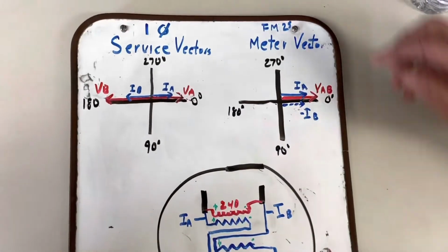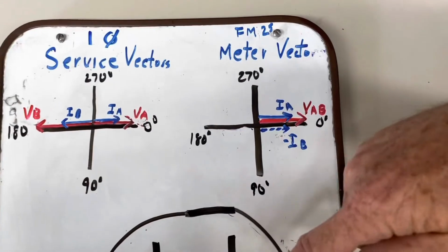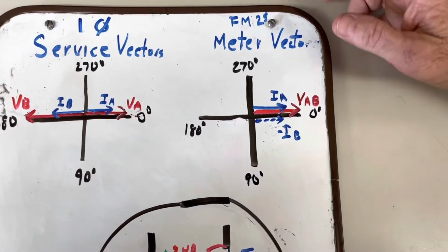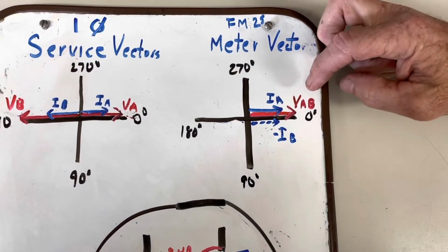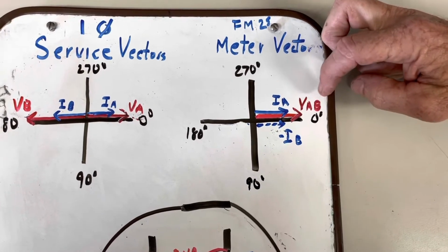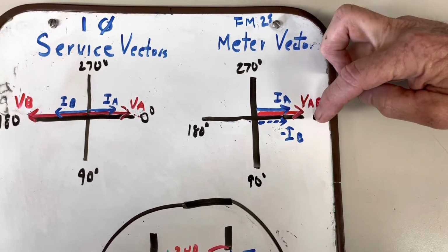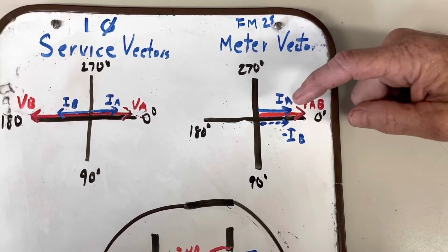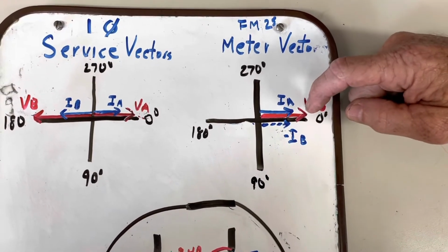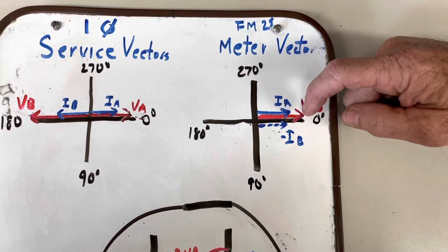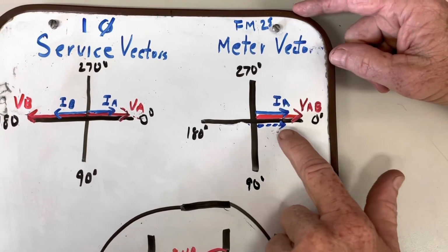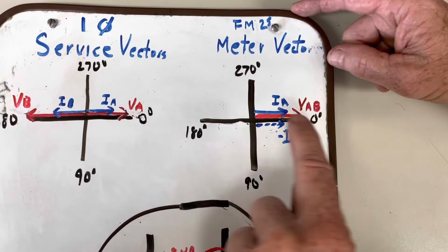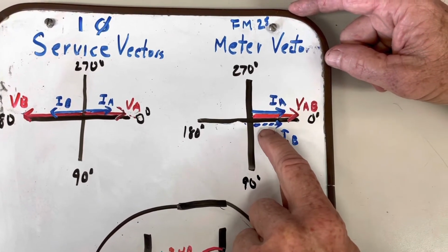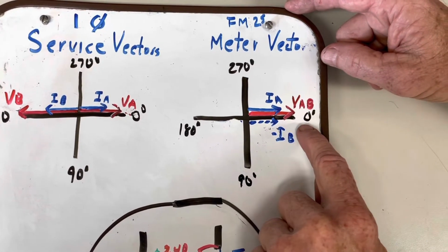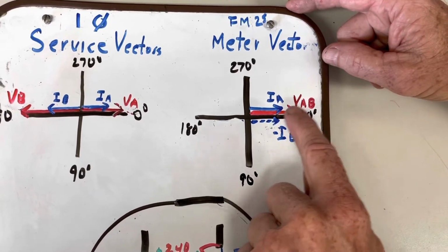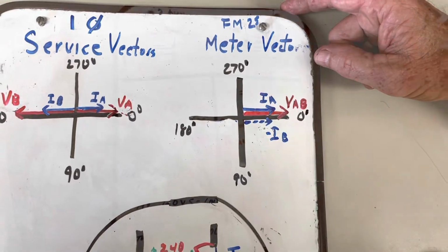If you look up here on the meter vectors, this is actually showing the meter form and what it's doing. We're using voltage A and B together at 240, and it's showing at 0 degrees. Then current A is already at unity at 0 degrees, so we didn't have to do anything to that. But this dotted line right here shows that I took this current and flipped it 180 degrees and put it on this same 0 degree path. So now the meter will meter it correctly.